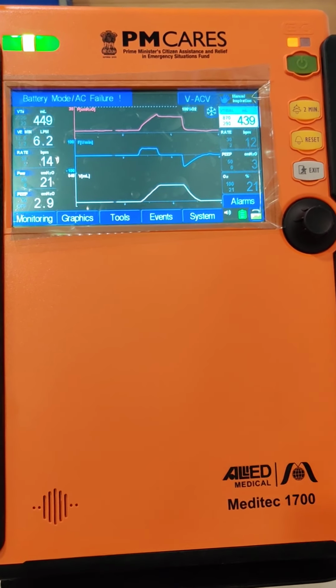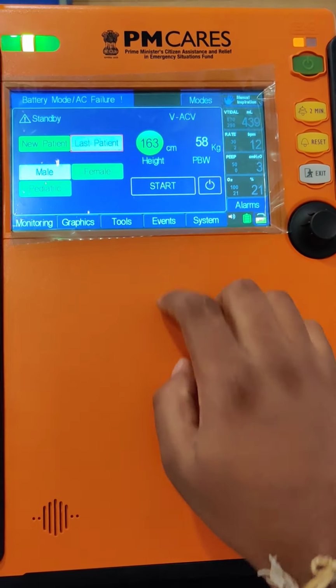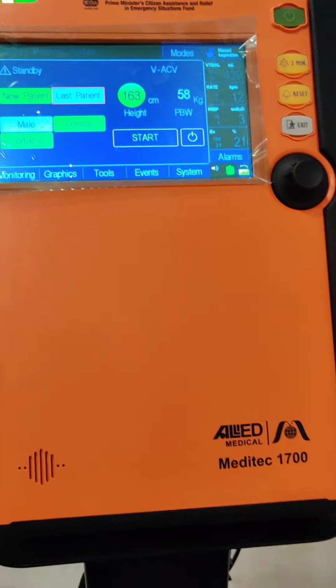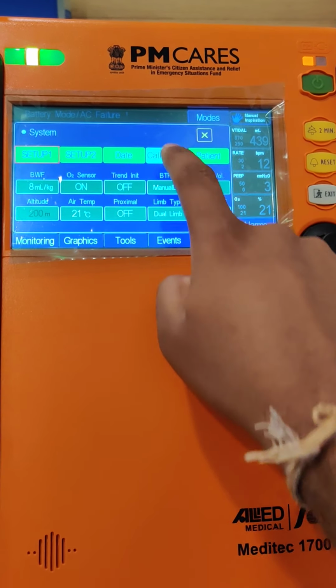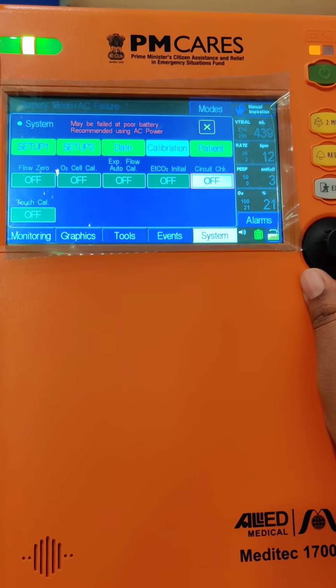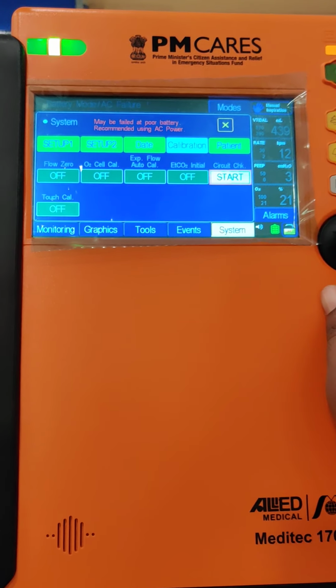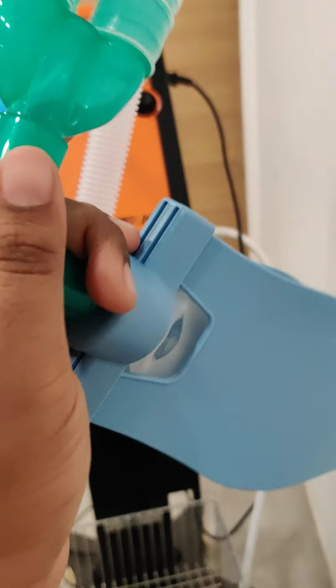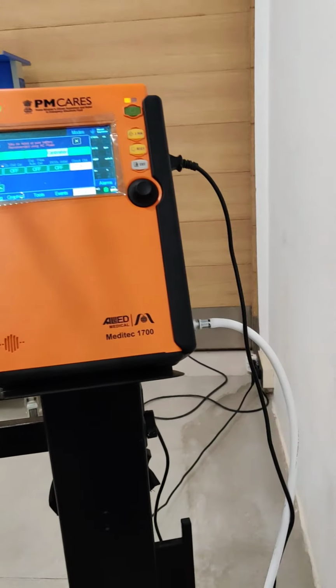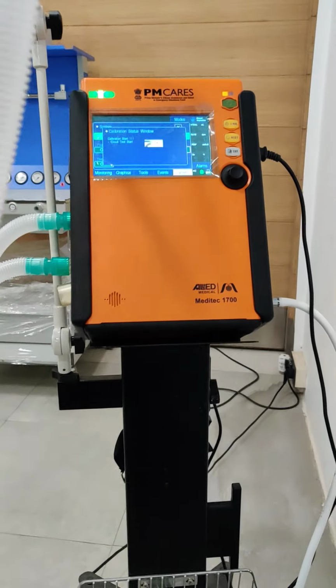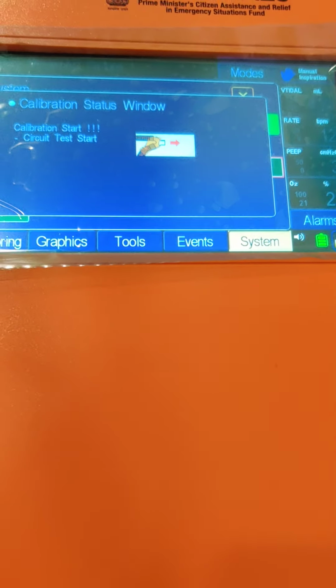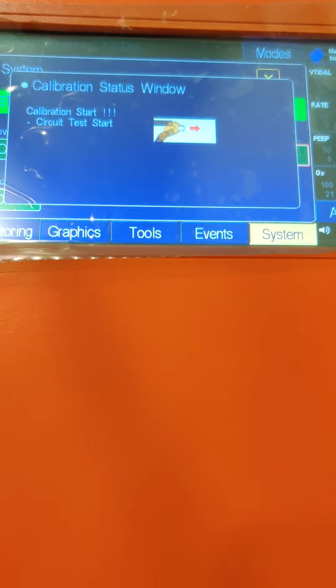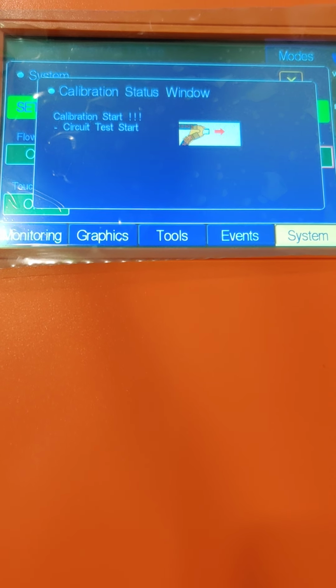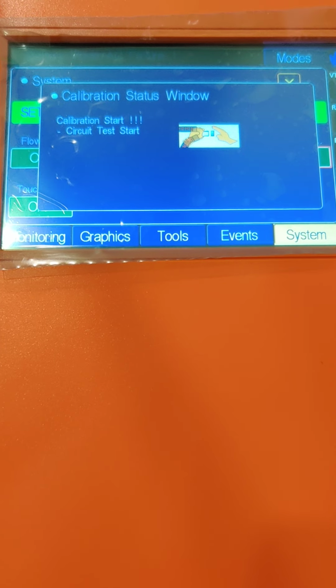Now for the circuit check, you have to put this ventilator into the standby mode. Now it has come to the standby mode, and now you have to go into the system. Then you have this calibration window over here. Then you have the circuit check. You have to select the start option, and then you have to occlude the Y-piece of the patient circuit when it shows on the screen. It will display when to occlude the Y-piece. Now it is showing to occlude the Y-piece. I have occluded the Y-piece like this.